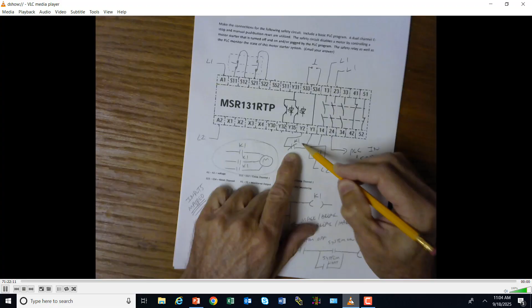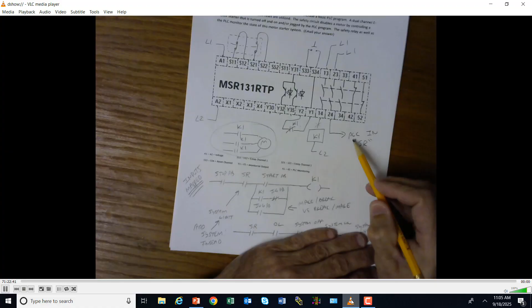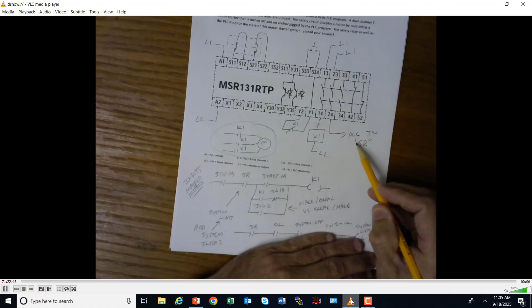The PLC tag is called SR. Okay, so if this is up, I have the opportunity to turn on the contactor if that's what I want to do. But if it's off, it doesn't matter if the PLC turns on the contactor or not. I will not get voltage here. And same thing, if this is on, I'm getting a signal to the PLC that I can go ahead. And if it's off, then the PLC will know that the safety relay is down.